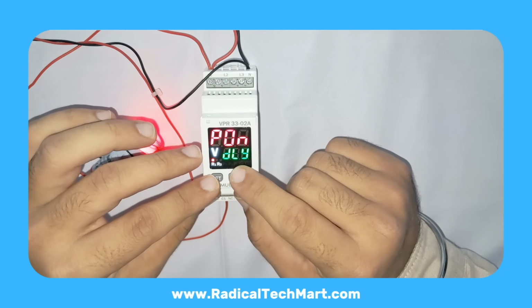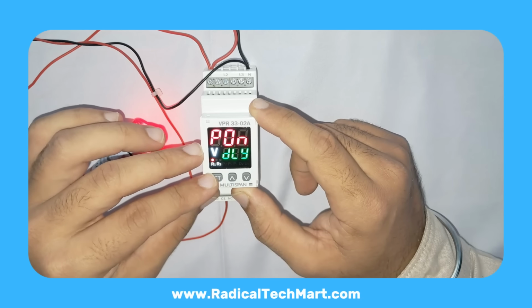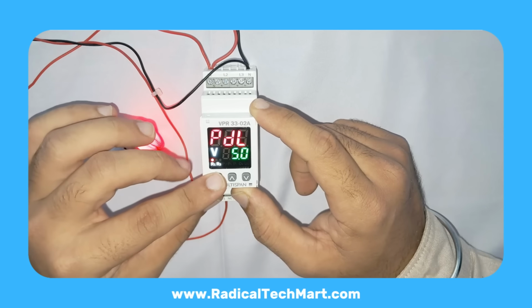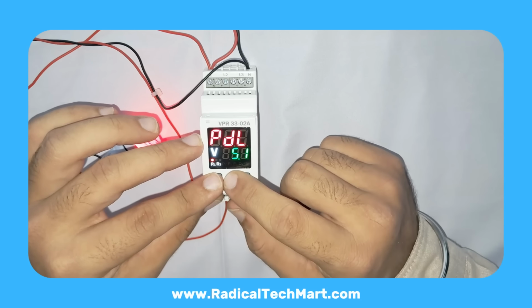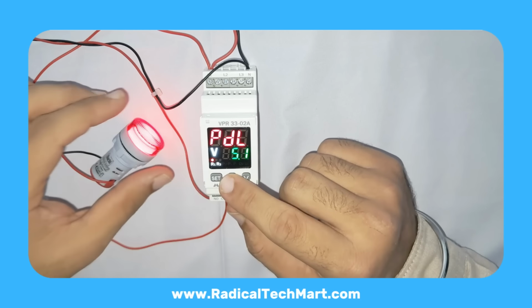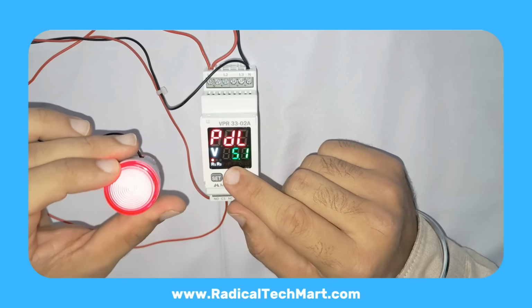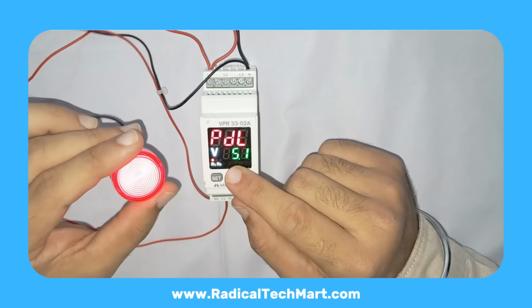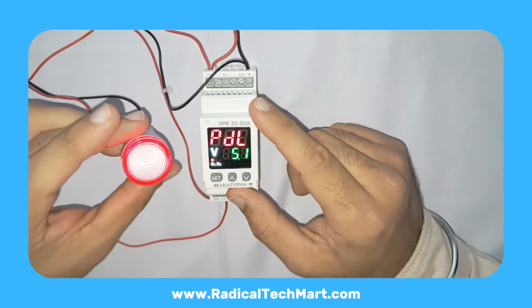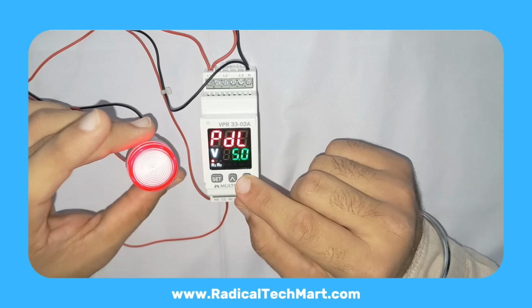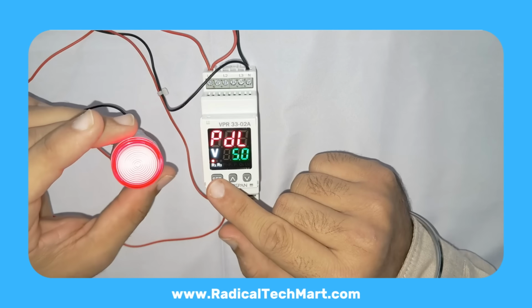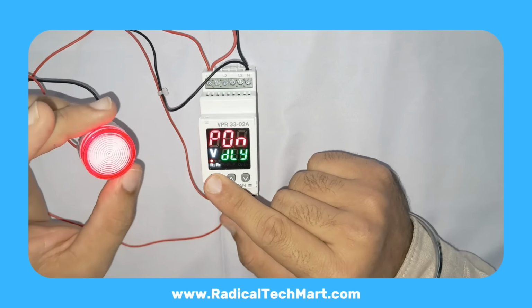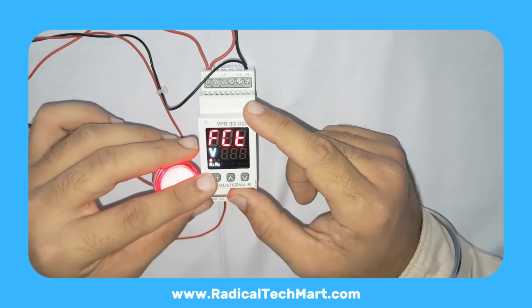Power on delay. Press up again. Now you get POD, power on delay. This is the delay when the device is first powered up. The default could be 5 seconds. That means even if the supply is healthy, the relay output will turn on 5 seconds after power up. You can increase or decrease this time as per your load requirement. Press Set.